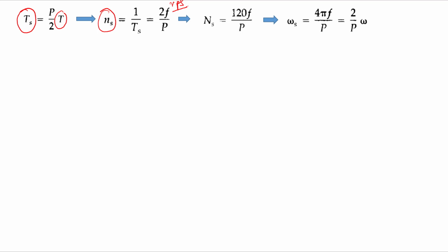So Ns becomes - if you know the supply frequency and the number of poles per phase in the induction machine from the constructional features, we can find the synchronous speed at which the flux rotates in the periphery of the armature surface: 120 F by P. Converting to omega, omega S equals 4 pi F by P, which is equal to 2 by P times omega. This is the expression for synchronous speed.